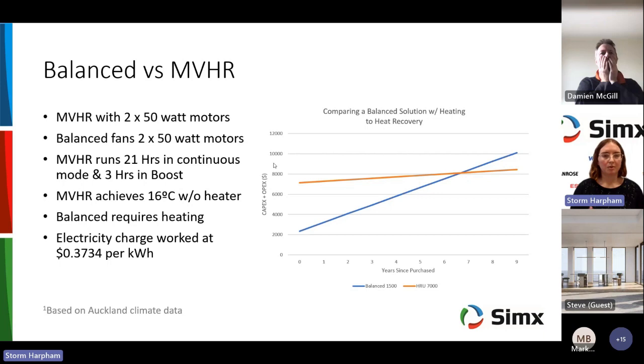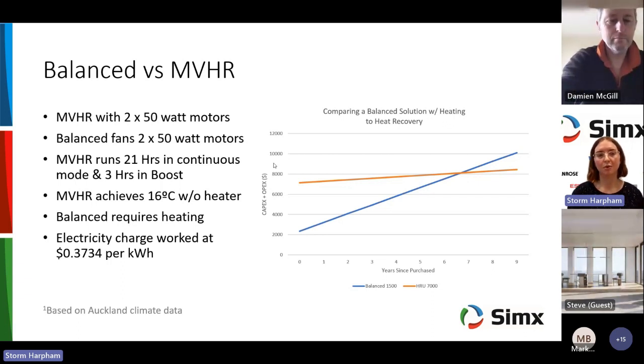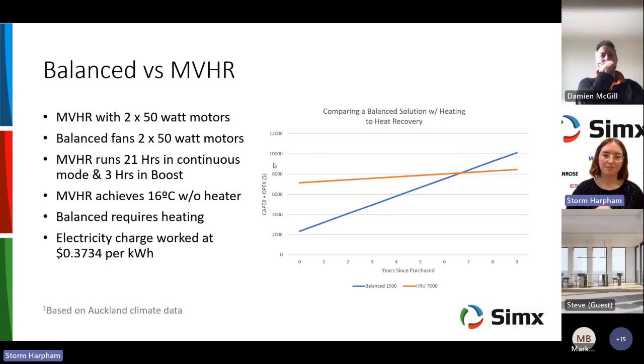What we looked at was the power usage of those systems, and said if they were running 21 hours in continuous mode and 3 hours in boost mode to deliver the requirements for those wet rooms. We wanted to achieve 16 degrees without a heater for the MVHR, whereas we knew that balanced would require a heater no matter where it was in the country to get up to 16 degrees, although the data here is based on Auckland conditions.